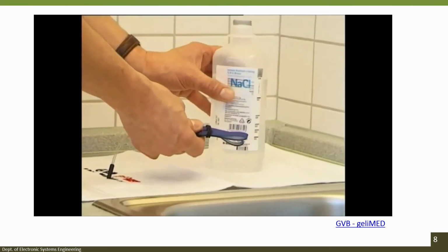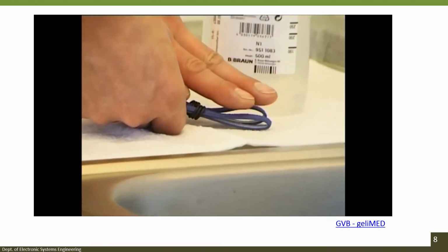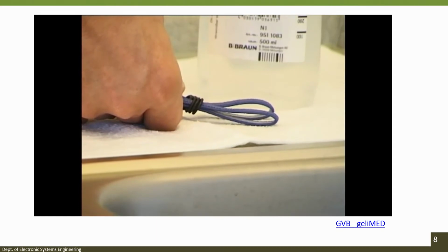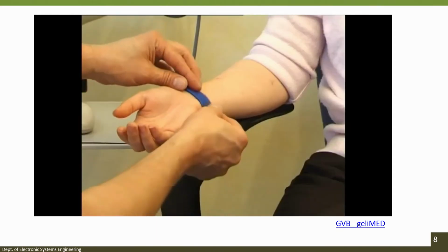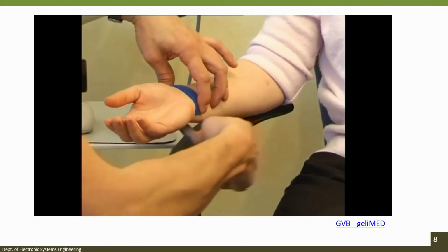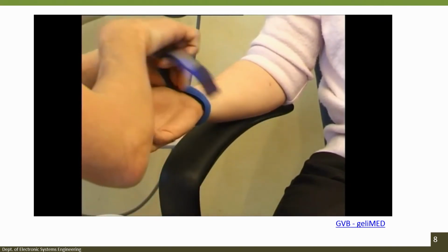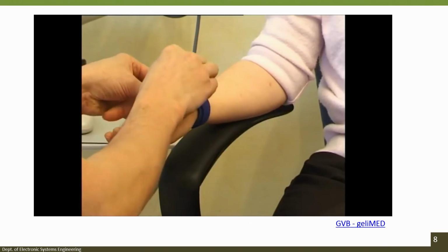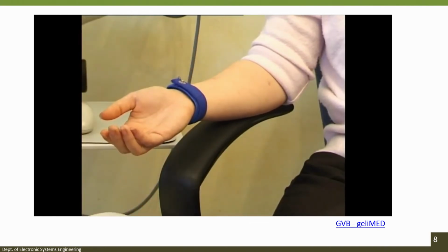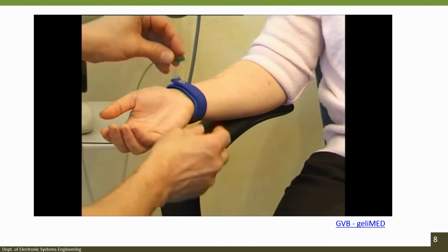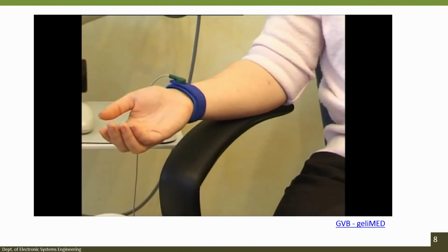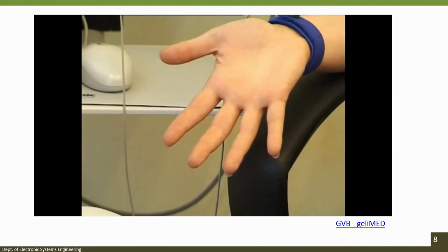The electrodes must also be moistened with NaCl when stimulating with finger-toe stimulation electrodes. However, the electrodes should not be wet. Therefore, dry the electrodes with a cloth. A ground electrode is also placed over the wrist between the stimulation electrode and the stimulation area prior to connection to the EMG instrument when using stimulation in sensitive neurography with finger-toe stimulation electrodes.